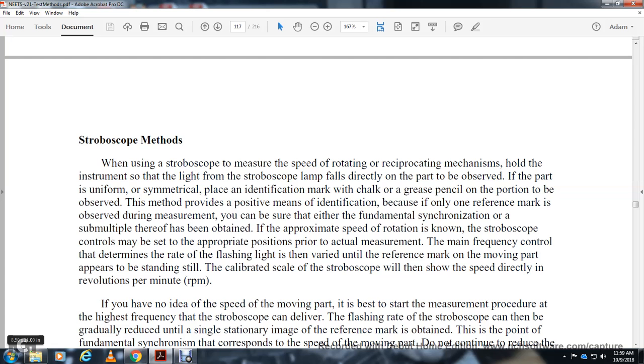The stroboscope method. The stroboscope is used to measure rotating and reciprocating mechanisms. The light from the stroboscope lamp will fall directly on the part to be observed. If the part is uniform and symmetrical, place an identification mark with chalk, grease pencil, or pencil on the portion to be observed. This provides a positive means of identification because there is only one reference mark. During the measurement, you can see either the fundamental synchronization or a submultiple of it.